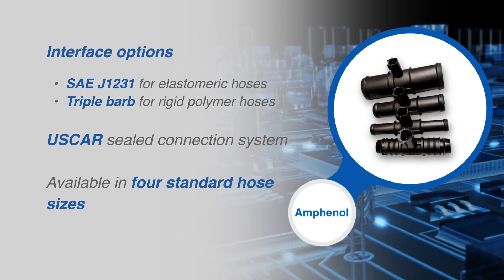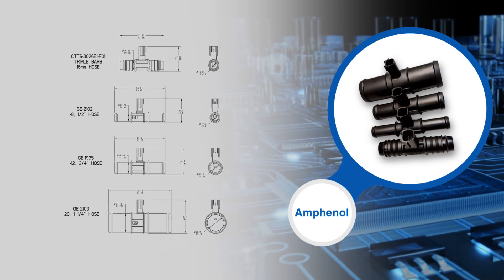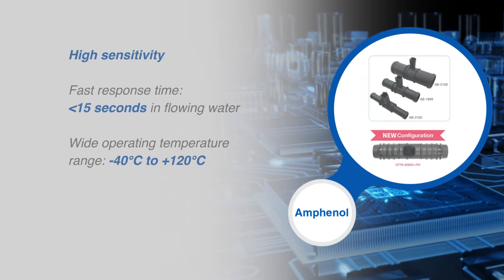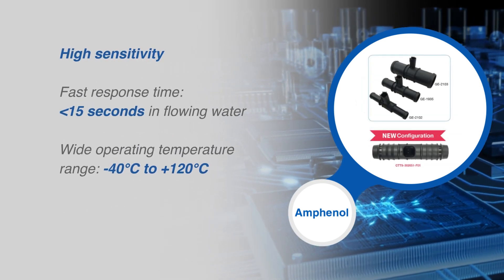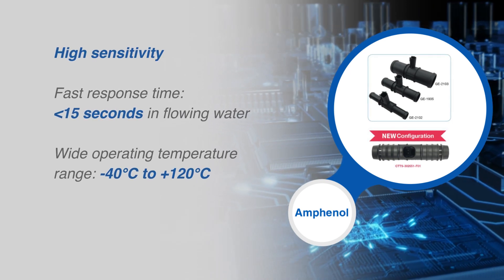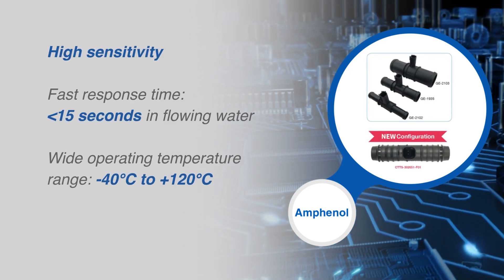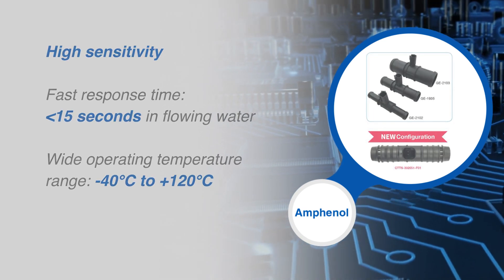These flow-through temperature sensors use the USCAR Sealed Connection System and are available in four standard hose sizes. The inline flow-through temperature sensors feature high sensitivity, a fast response time of under 15 seconds in flowing water, and a wide operating temperature range of negative 40 to 120 degrees Celsius.